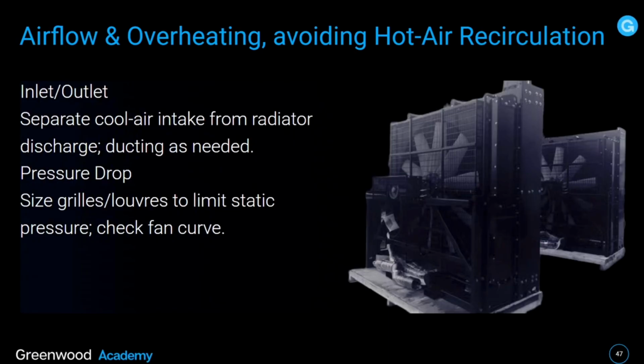And of course, and I've mentioned it a few times, avoiding hot air recirculation. Inlet, outlet. Separate cool air intake from radiator discharge. ducting as needed. Pressure drop. Make sure to take into consideration the size of the grills and the louvers to limit static pressure. Check the fan curve, which starts to get fairly technical.